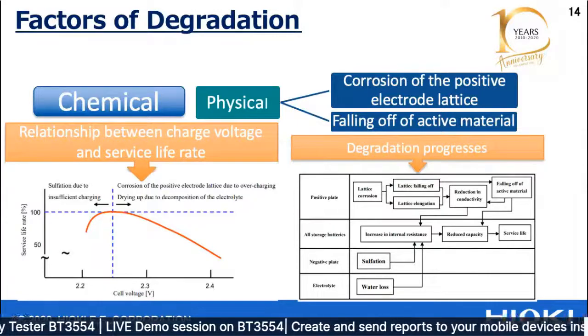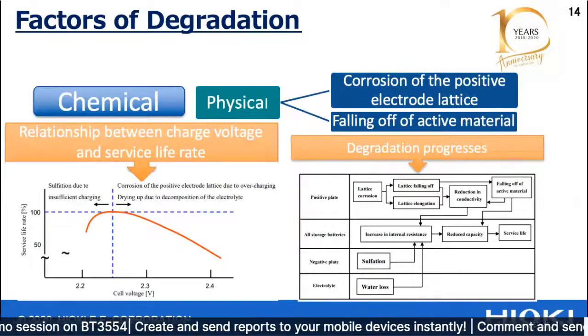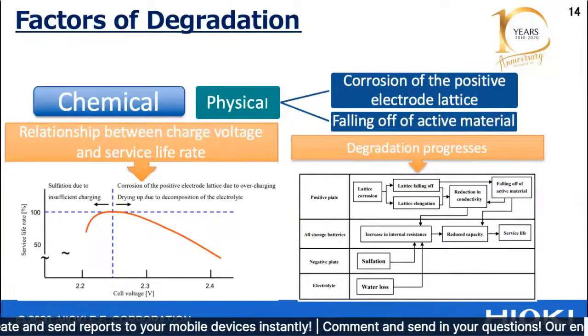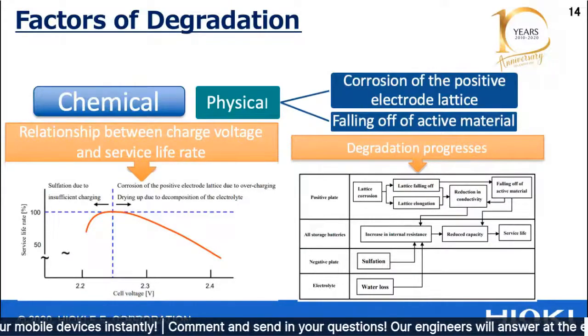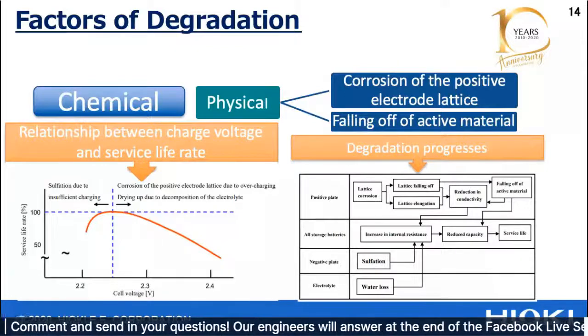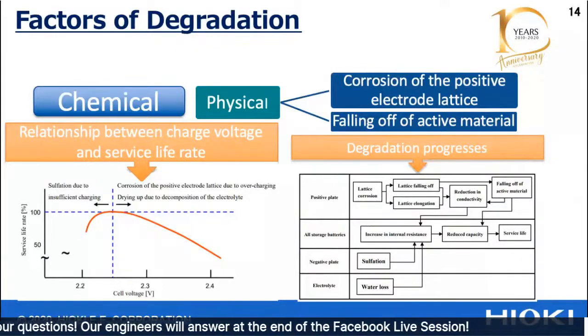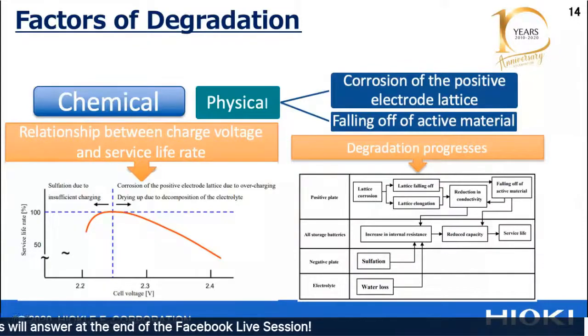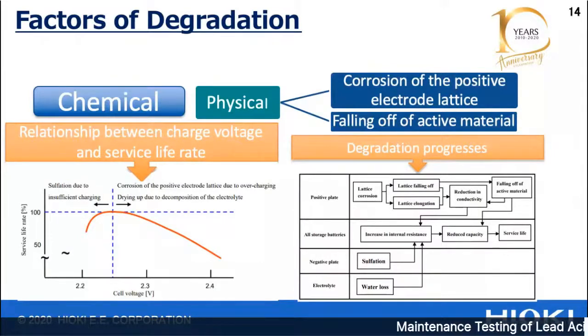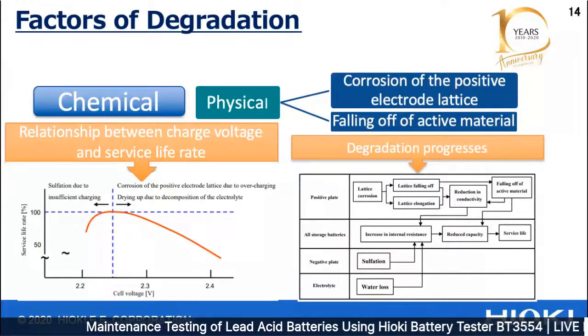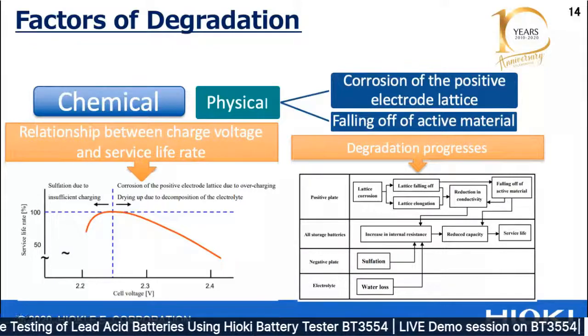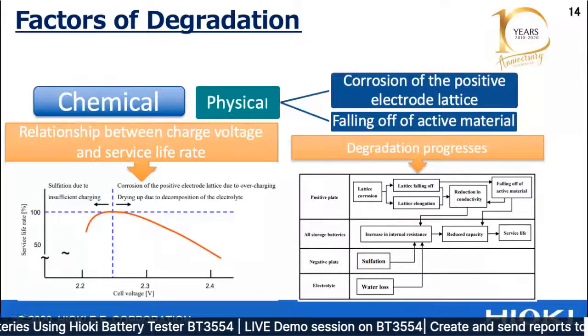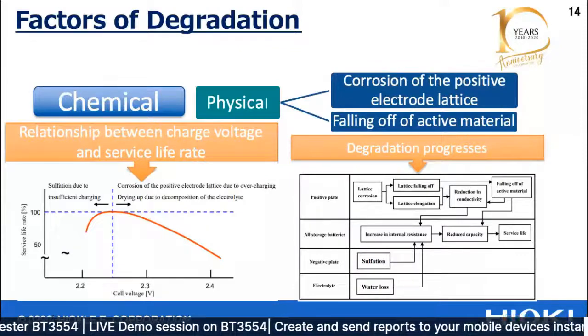The discharge causes the lead in the electrode to become lead sulfate. But when this happens, it develops a stable crystal structure over time, which we call sulfation. Since lead sulfate becomes less conductive once it crystallizes, it will not revert to lead, even if the battery is charged. When lead sulfate crystals adhere to the surface of the negative electrode, the reaction area between the electrode and the electrolyte decreases, causing the internal resistance of the battery to increase. Also, the concentration of the electrolyte decreases, causing a voltage drop.